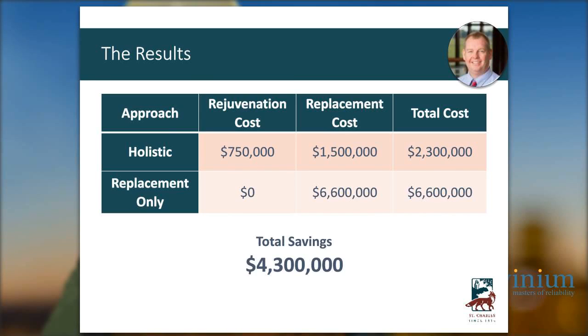In terms of dollars, here's how that works out: even though only a fifth of the cable had to be replaced, that one-fifth cost double what it cost us to inject the other almost 200,000 feet. So if we had not selected a hybrid approach prioritizing injection first, that would have been well over $6 million. But we would have never spent $6 million, because we would have never gotten that budget, and we would have never had enough manpower to support doing that much cable replacement in the last 5 years.